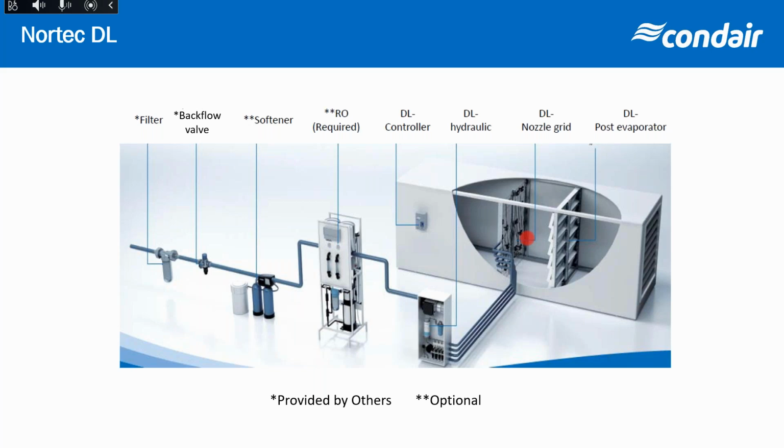Just some design criteria. We don't want to exceed about more than 690 feet per minute. There's no aerosols. There's nothing that gets past the ceramic media. But we're very obsessed with hygiene. So we know about CSA and other things in hospitals, and we respect that. But we're obsessed with hygiene. So that's why we use RO water and or even DI.